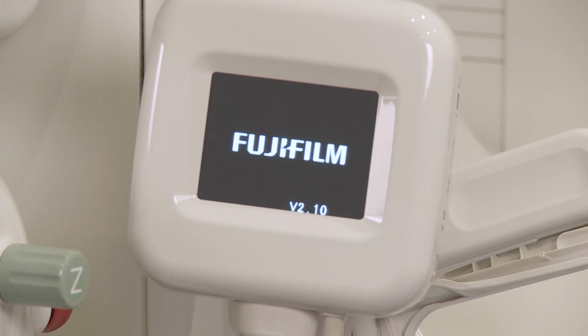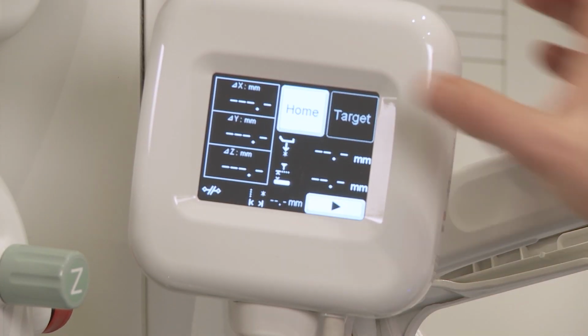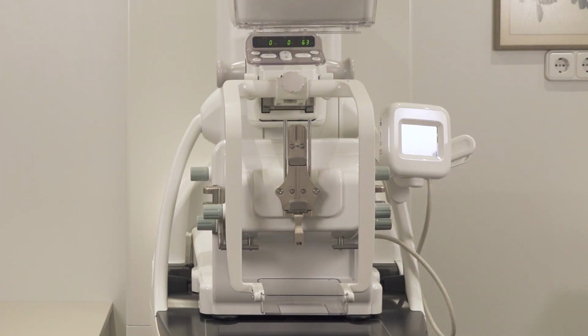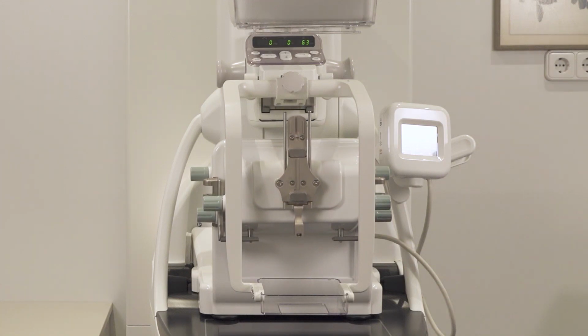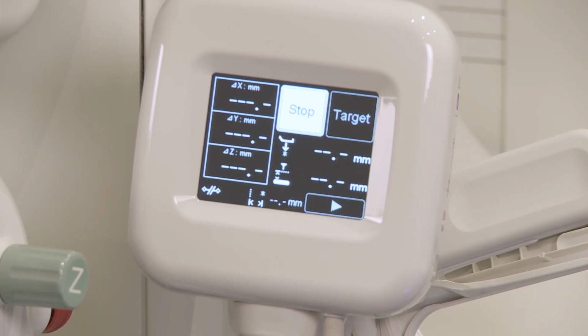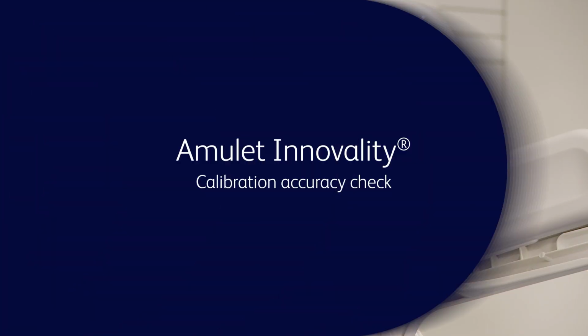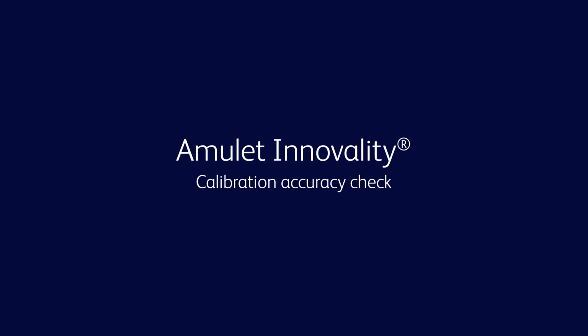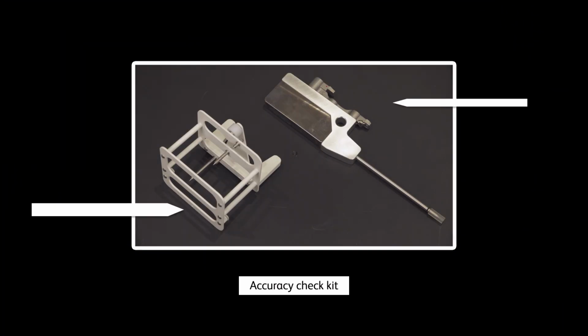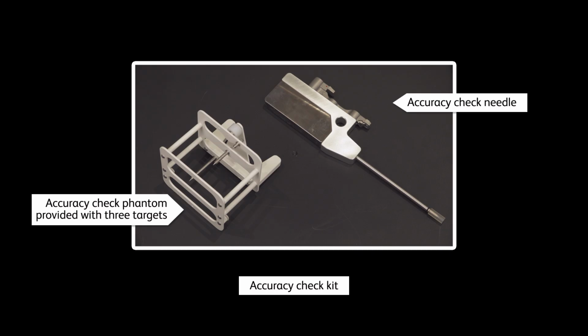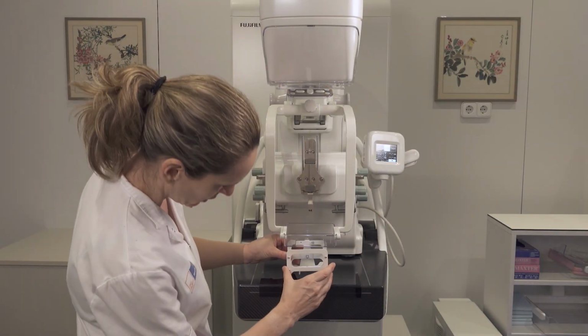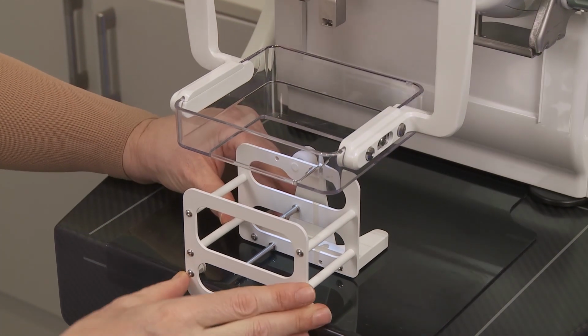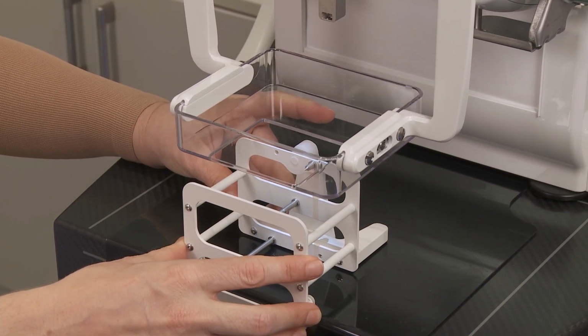Initialization takes a few seconds. Press the Home button to drive the positioner to home position. Press Stop at any time to stop motion if needed. Calibration accuracy check. Steps to follow. Place the accuracy check phantom over the breast support as shown and apply a light compression.